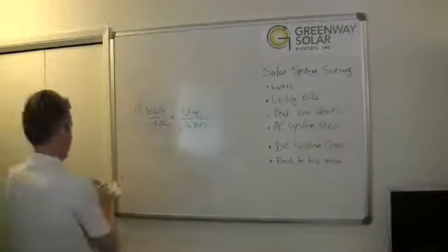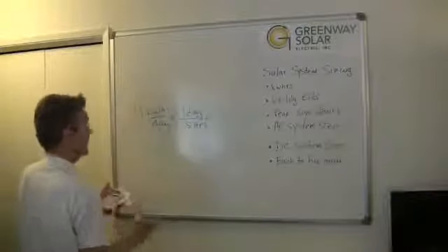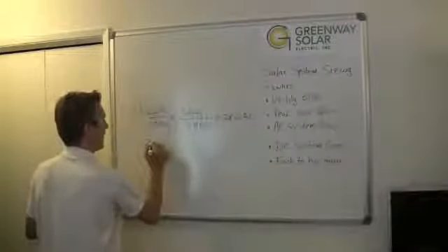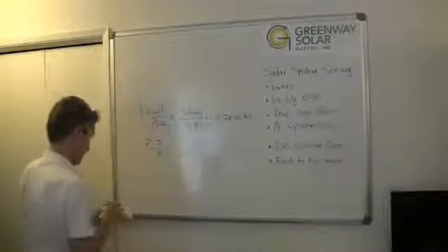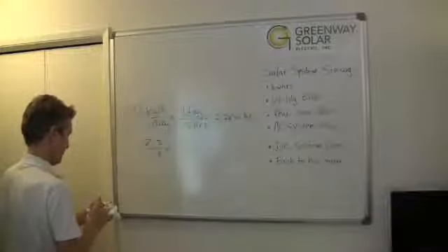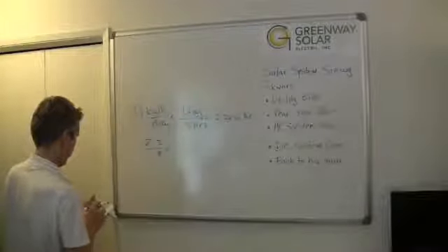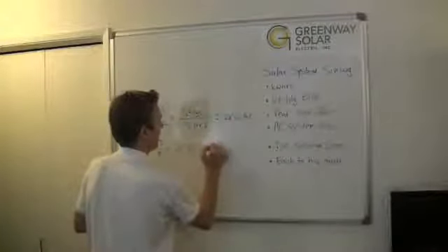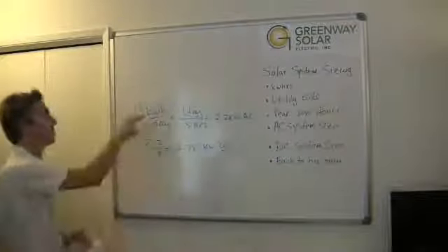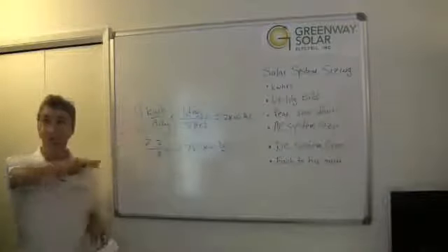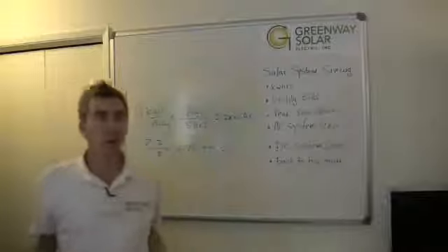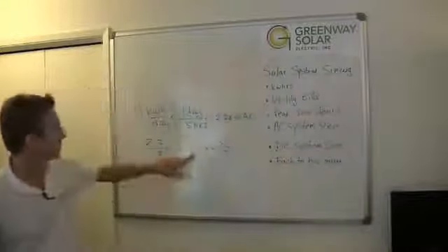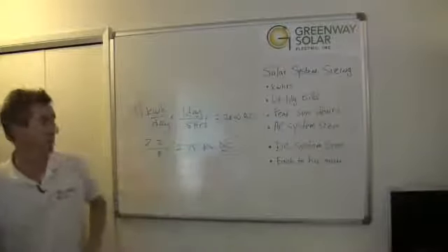All right, so 11 divided by 5 is 2.2 kilowatt AC system. We're now going to divide that by 0.8. Oops, 2.2 divided by 0.8. 2.75 kilowatt DC system. So she uses a lot less power, in other words, to get a bill of basically zero because she's producing all her power herself. She would need a 2.75 kilowatt DC system, substantially smaller.